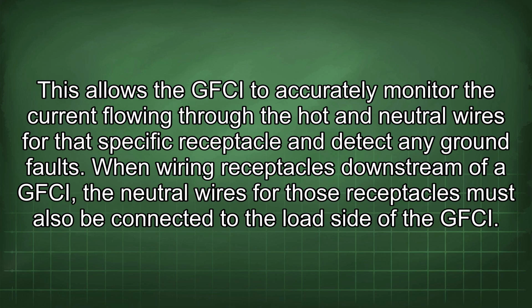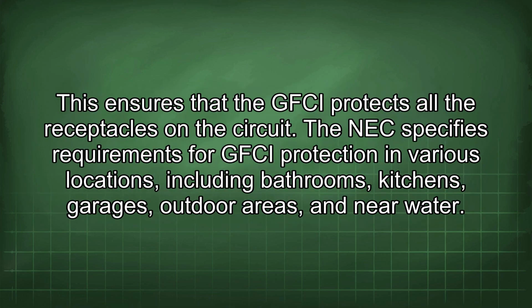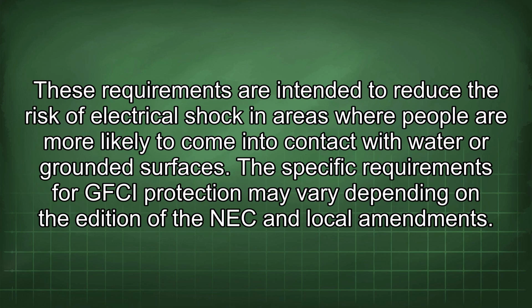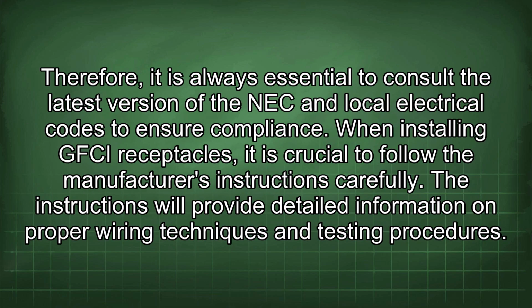When wiring receptacles downstream of a GFCI, the neutral wires for those receptacles must also be connected to the load side of the GFCI. This ensures that the GFCI protects all the receptacles in the circuit. The NEC specifies requirements for GFCI protection in various locations, including bathrooms, kitchens, garages, outdoor areas, and near water. These requirements are intended to reduce the risk of electrical shock in areas where people are more likely to come into contact with water or grounded surfaces. The specific requirements for GFCI protection may vary depending on the edition of the NEC and local amendments. Therefore, it is always essential to consult the latest version of the NEC and local electrical codes to ensure compliance.